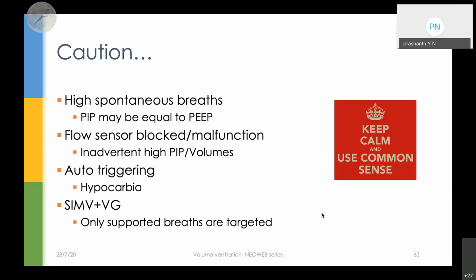So one of the solutions could be to switch to SIMV, so that some of the breaths are assisted by the ventilator along with the VG. Then there is the flow sensor being blocked or malfunctioning. Suppose you have ventilated a baby on VG and given surfactant; you know that the PIP required by the baby should actually come down.